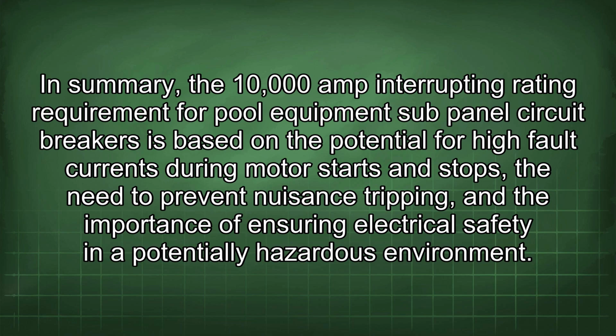In summary, the 10,000 amp interrupting rating requirement for pool equipment sub-panel circuit breakers is based on the potential for high fault currents during motor starts and stops, the need to prevent nuisance tripping, and the importance of ensuring electrical safety in a potentially hazardous environment.